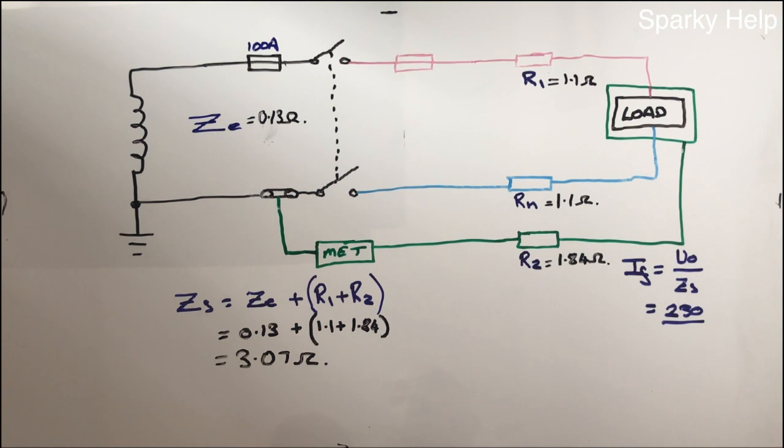So this will give us a value of 0.13 for ZE plus 1.1 plus 1.84 gives it a grand total of 3.07 ohms. So that is ZS for this particular circuit, which now allows us to calculate the fault current.